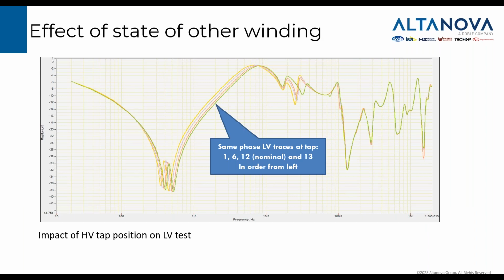Tap changer located on high voltage side can also affect traces of low voltage side, even if it's not in the same circuit. There are apparently couplings that make it visible, and this is a number of tests which I did once to confirm it. So this is LV trace measured on the same coil several times on the same day, same conditions, but with different tap positions. Tap changer was located on high voltage side. This is low voltage winding, and we can see the traces change from one position to another position as tap changer was changing. And also that changeover selector made additional changes here. This is the green line when tap 13 was one tap after the nominal tap position. As you see, 12 was nominal. So you need to be aware of this as well.